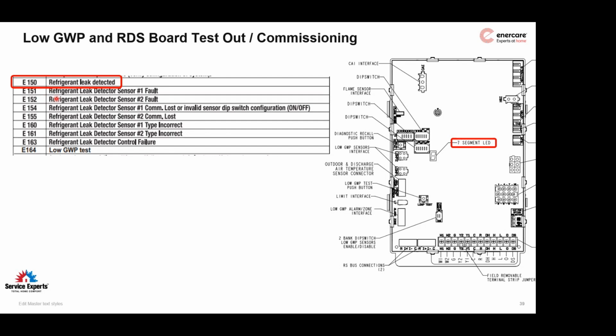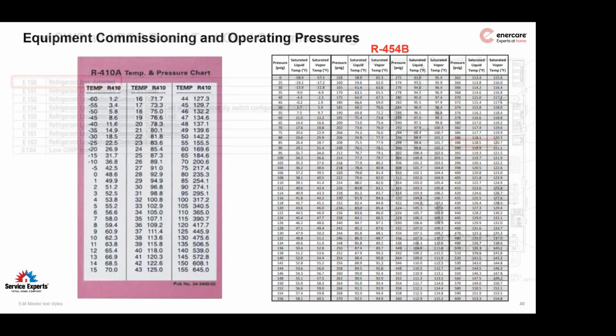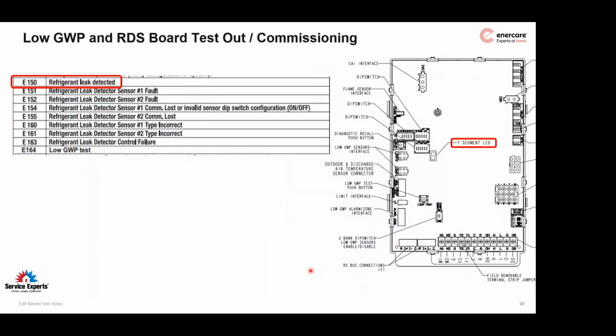And the process is the same with this. Exact same thing. Use the test button. Sorry, I'm going to back up one right here. Use the test button on this board right next to the dip switches, which is over here, the low GWP test button. Same process, and it'll go through. You'll see on the 7-segment display, the fault will display. Same process, though.